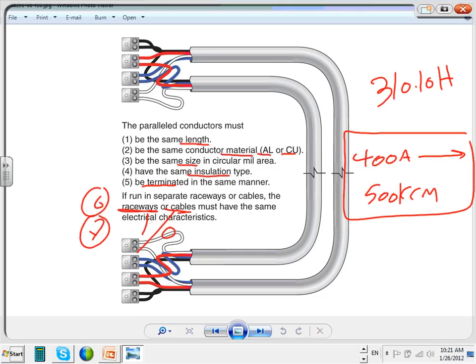What's the minimum conductor that I can parallel? 1/0. Why do we parallel? Because it's a nightmare not to. Pulling a 2000 kcm conductor in a conduit, I don't know if you can find a conduit to house 4 of them, or 3 of them plus a derated neutral. Any question, guys, about paralleling? The paralleling happens to every phase.